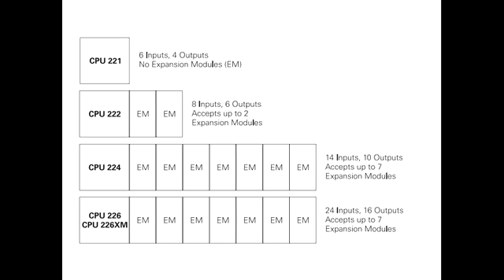The 222 will accept up to 2 expansion modules. The S7-224 comes with 14 digital inputs and 10 digital outputs. The 224 will accept up to 7 expansion modules. The S7-226 and S7-226XM come with 24 digital inputs and 16 digital outputs. The 226 and 226XM will accept up to 7 expansion modules.